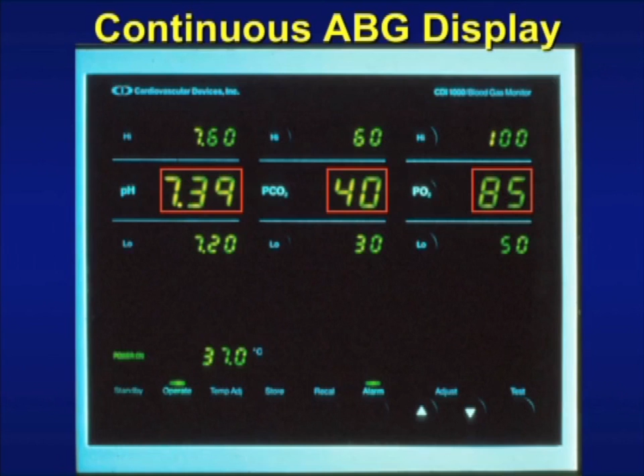Here is an actual case that I did back at Irvine, and this supports the idea that we would want to have these in every operating room. The continuous line is the PO2, it says O2 over here on the left, from the Optode. The little pluses here are data points from arterial blood gases sampled from the cannula and sent to the laboratory in the usual way. And you can see two things from this. One, the Optode and the blood gases were very close together, so the Optode was functioning quite well in measuring the PO2. But two, something happened in this case. Here's the Optode in room air, reading room air PO2, which is about 147. It's put into the patient's artery, and it's measuring his arterial PO2. He's on 100% oxygen, so that goes up to 500.